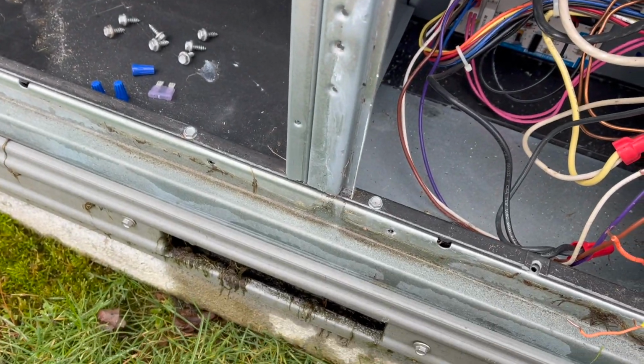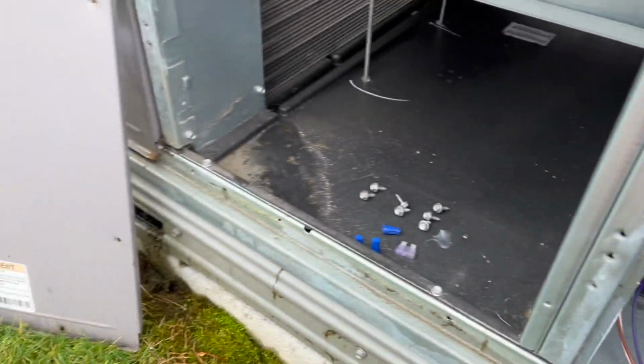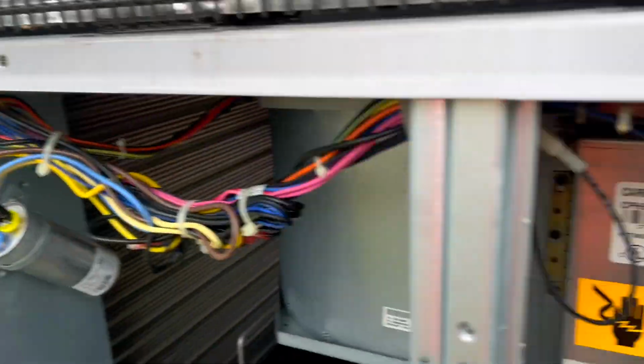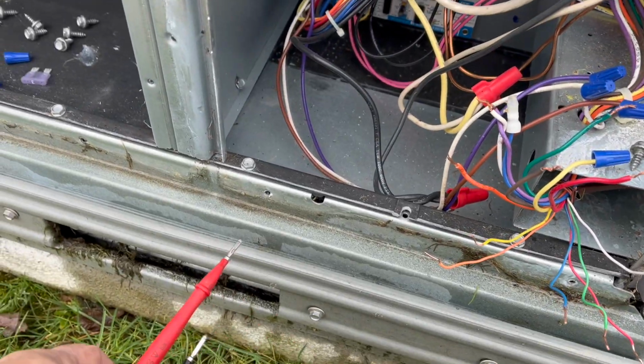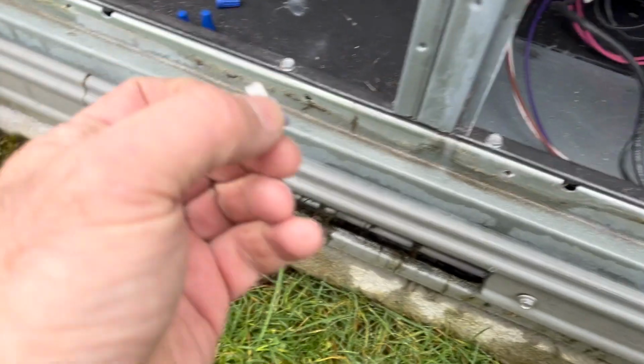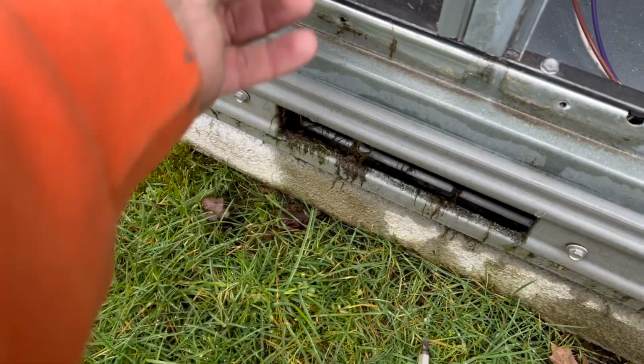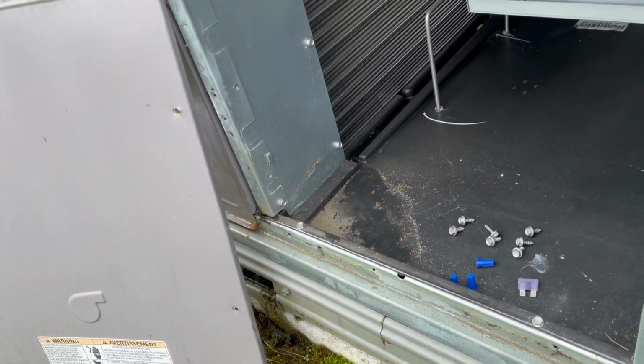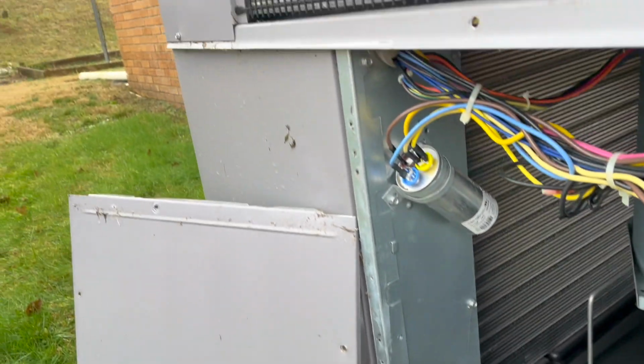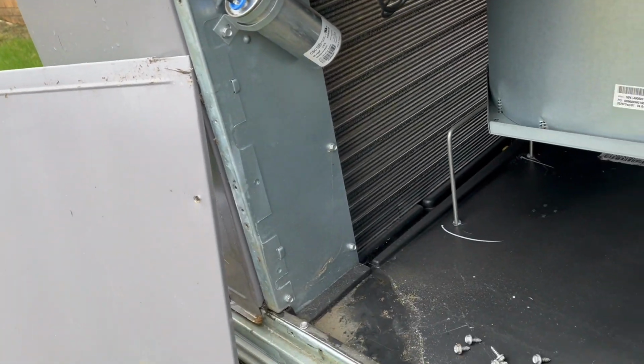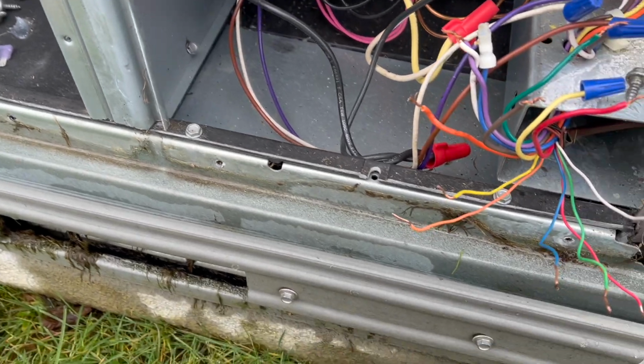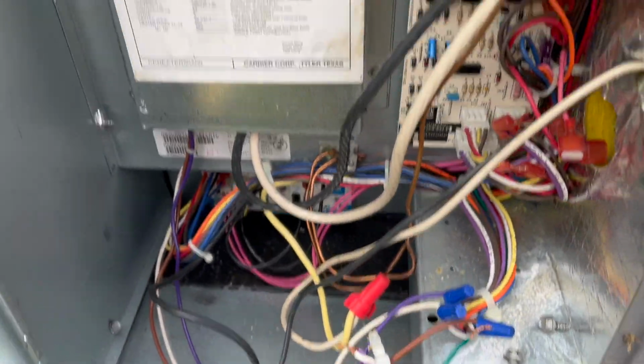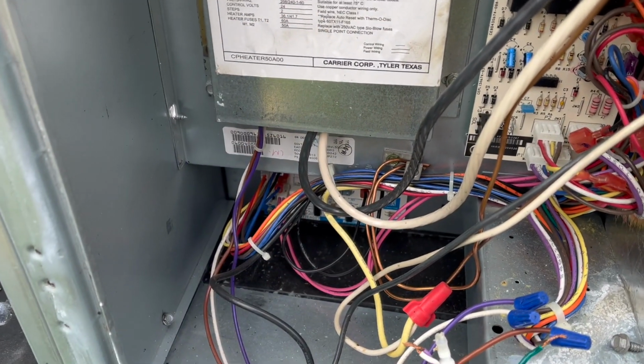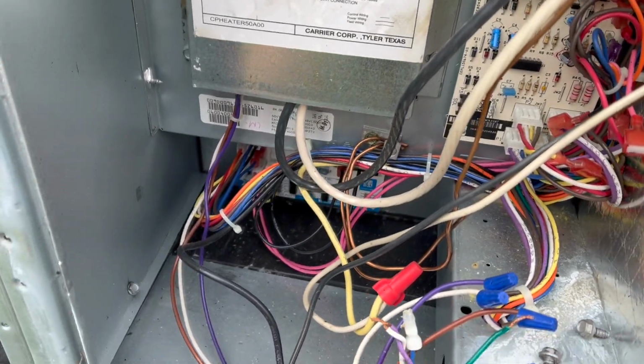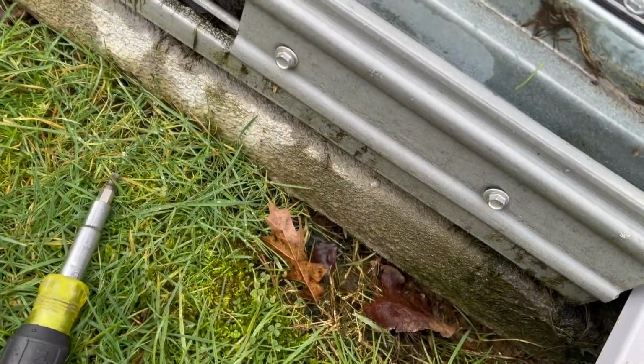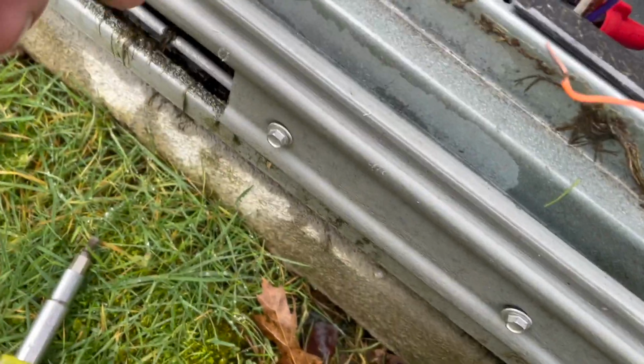Well, this is strange. I'm out here working on a Comfort Maker Carrier product package unit, and when I got here, the fuse was blown. So I did the usual Carrier stuff and started going through all of the control wires, seeing where there was one rub, and I couldn't find anything. So I could smell a little something burning here, so I checked the transformer, and I'm getting 24 volts off the transformer, but that was to ground.